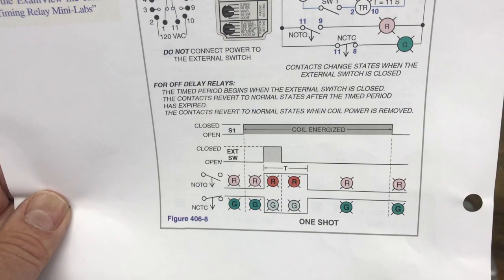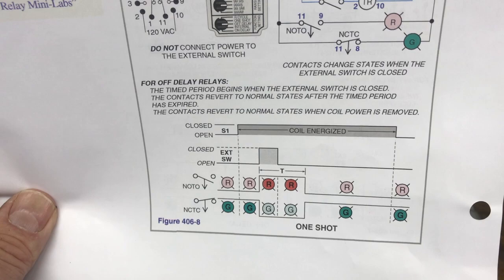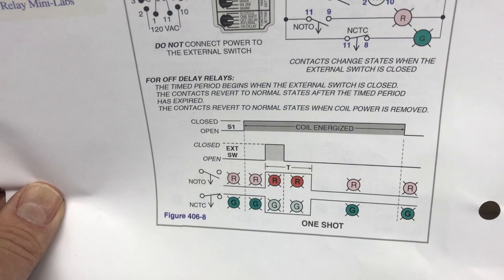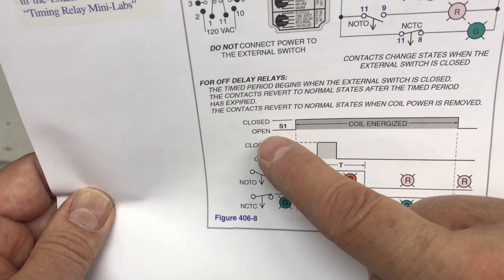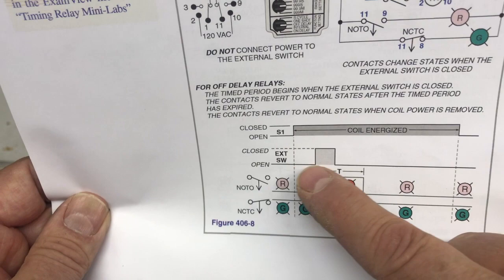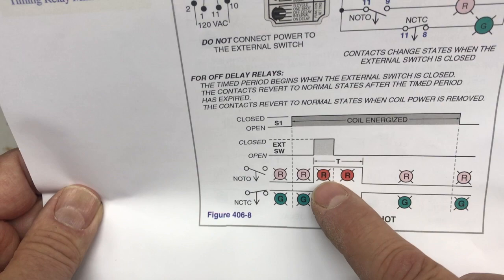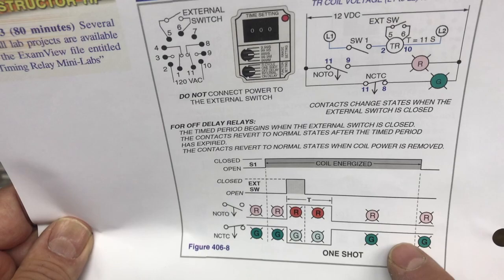So the off delay changes states after the opening of the switch; on the one-shot, it changes states when the switch is closed. For one-shot relays, the time period begins when the external switch is closed. The contacts revert to normal states after the time period expires, and also when coil power is removed. Switch one is closed here when the coil is energized — these are your starting states: normally open timed open, normally closed timed closed. When the external switch is closed, the time period starts, and after it expires the light goes out.